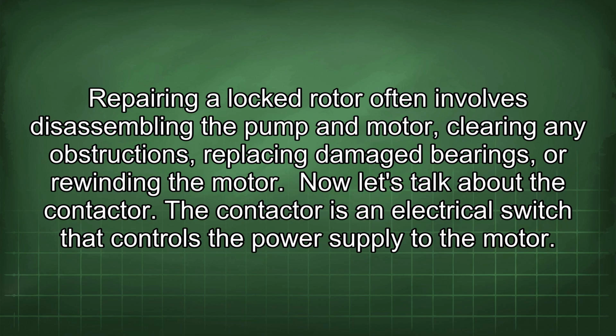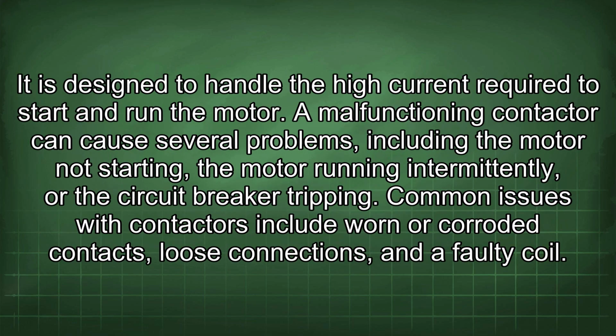The contactor is an electrical switch that controls the power supply to the motor. It is designed to handle the high current required to start and run the motor. A malfunctioning contactor can cause several problems, including the motor not starting, the motor running intermittently, or the circuit breaker tripping. Common issues with contactors include worn or corroded contacts, loose connections, and a faulty coil.